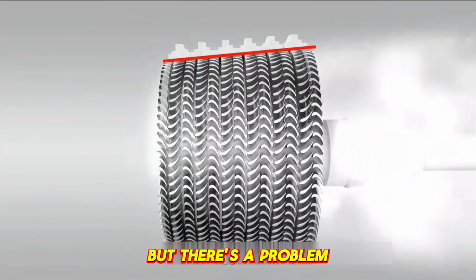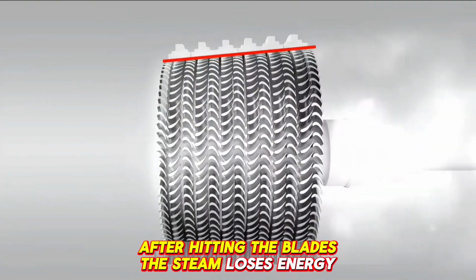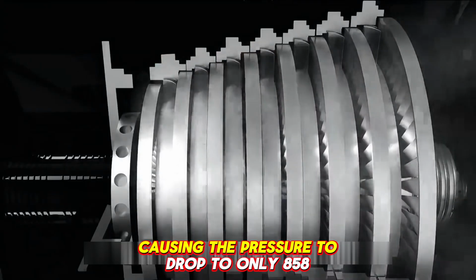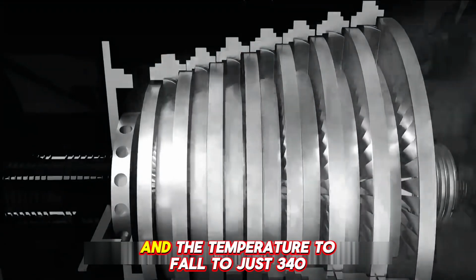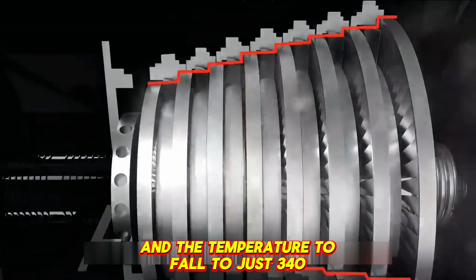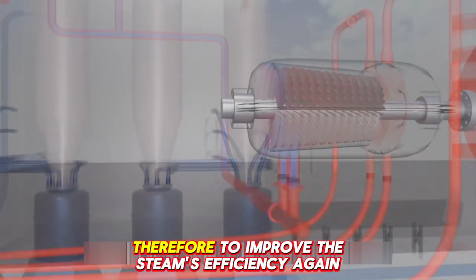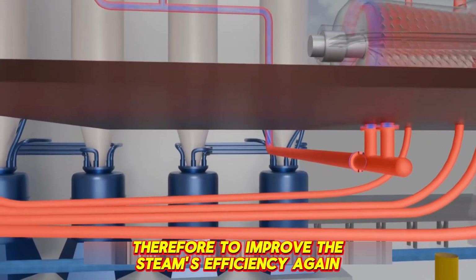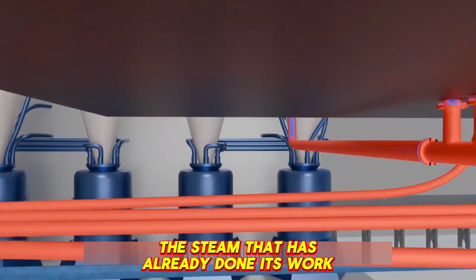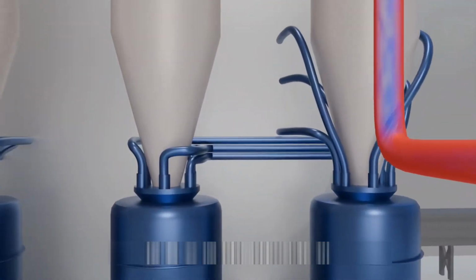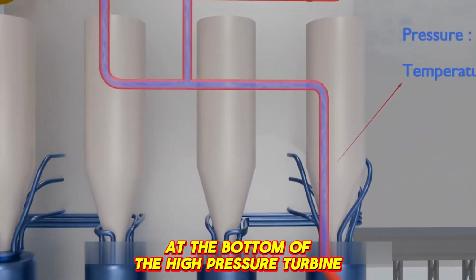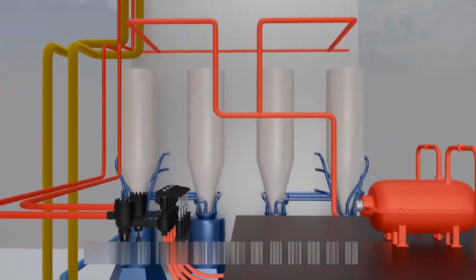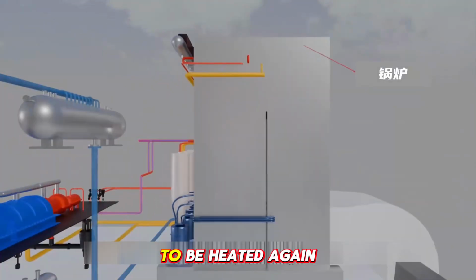But there's a problem. After hitting the blades, the steam loses energy, causing the pressure to drop to only 858 and the temperature to fall to just 340 degrees Celsius. Therefore, to improve the steam's efficiency again, the steam that has already done its work will then flow out through the steam pipe at the bottom of the high-pressure turbine. This steam will be sent to the reheater inside the boiler to be heated again.